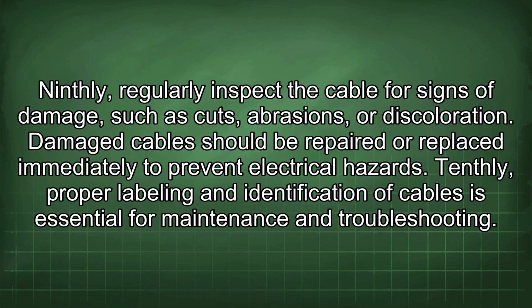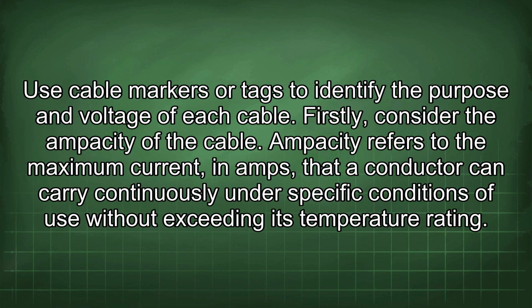Ninthly, regularly inspect the cable for signs of damage, such as cuts, abrasions, or discoloration. Damaged cables should be repaired or replaced immediately to prevent electrical hazards. Tenthly, proper labeling and identification of cables is essential for maintenance and troubleshooting. Use cable markers or tags to identify the purpose and voltage of each cable.